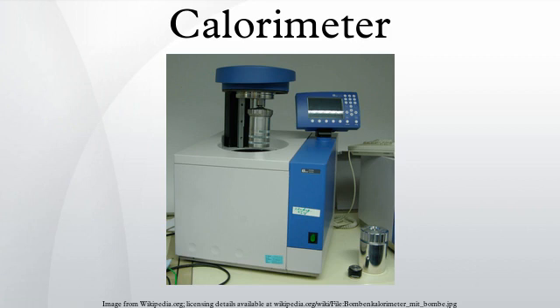The calibration of the calorimetric detectors is a key parameter and has to be performed very carefully. For Calvet-type calorimeters, a specific calibration, so-called dual effect or electrical calibration, has been developed to overcome all the problems encountered by a calibration done with standard materials. The main advantages are: it is an absolute calibration, standard materials for calibration are not necessary, the calibration can be performed at a constant temperature in heating or cooling mode, it can be applied to any experimental vessel volume, and it is a very accurate calibration. An example of a Calvet-type calorimeter is the C-80 calorimeter.